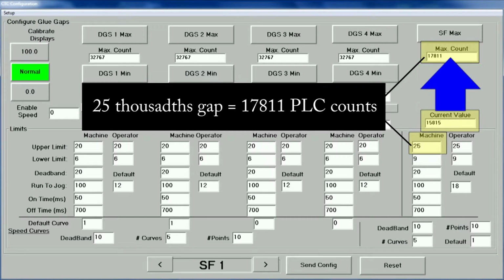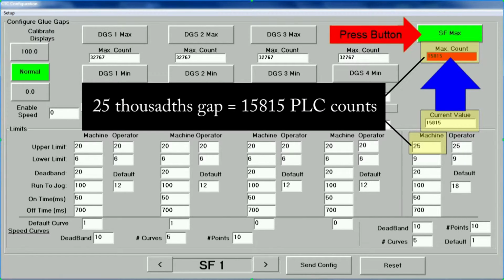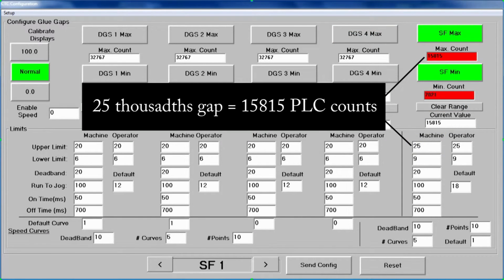To calibrate, we need to copy the sensor's current position value into the max count field. Simply press the SF Max button. The button turns green and the value turns red, indicating the value has been accepted. Now the gap equals 25 thousandths when the max count field equals 15,815.